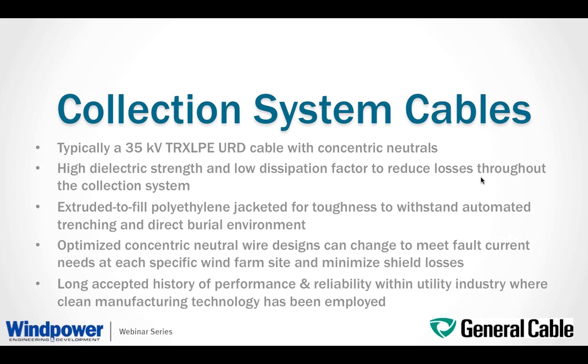Now going to the collection system cables. The 35 kV design portion is one of the most critical aspects of a wind farm project. The cable design used is typically a 35 kV TRXLPE insulated URD cable with concentric neutrals. The TRXLPE insulation offers a high dielectric strength and has the lowest dielectric loss characteristics of any other medium voltage cable or insulation type. I'll review the dielectric loss characteristics and the different types of insulation material in more detail later.